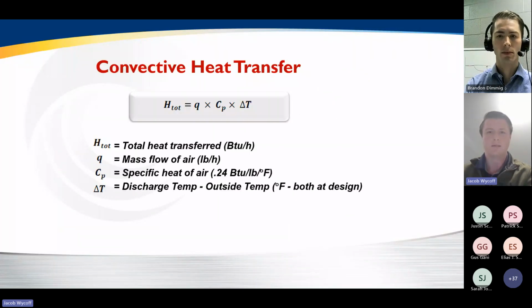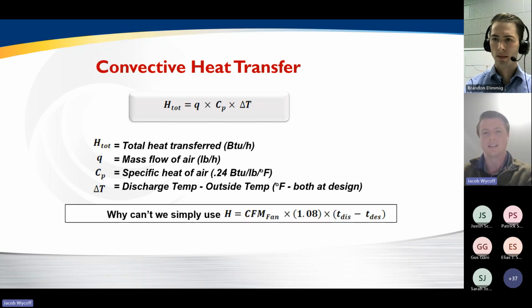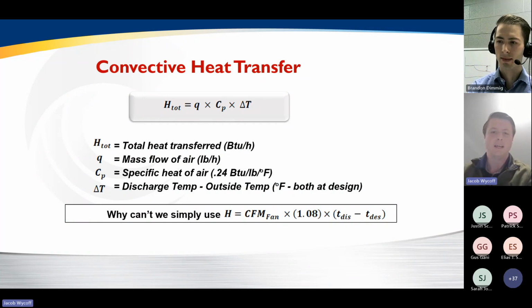And how is that? So raise your hand in the chat if you've used this in the past month or so, the convective heat transfer formula that governs our industry. Total heat transferred equals mass flow of air times specific heat of air times your delta T. So we actually have a few people that have used this in the past month or two. That's a little bit surprising because in our day-to-day, we typically see people using the formula down below. Total heat transferred equals volumetric CFM times 1.08 times your delta T.